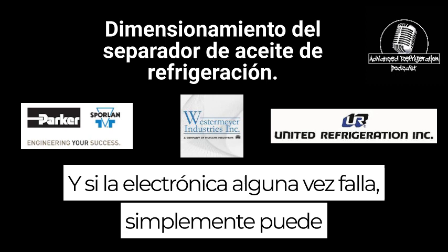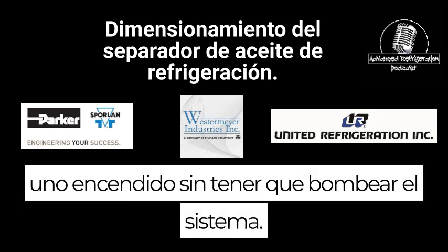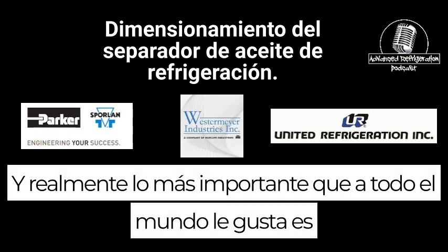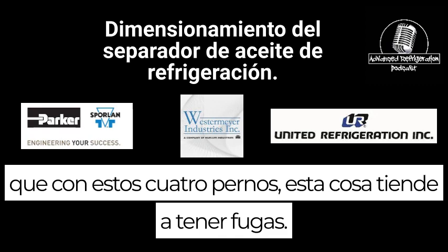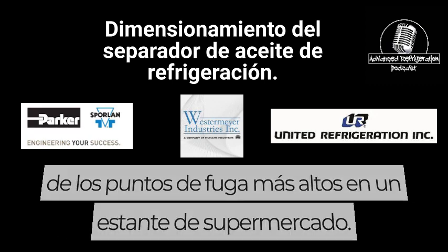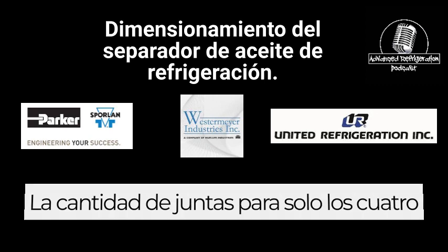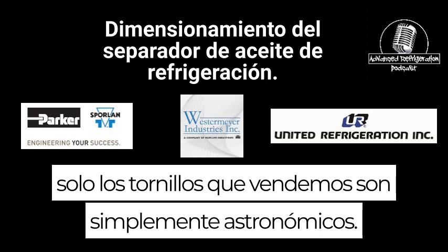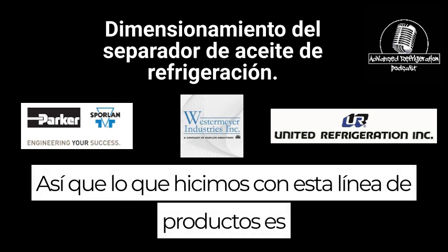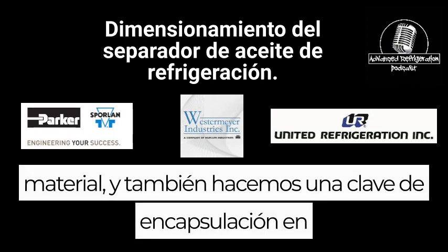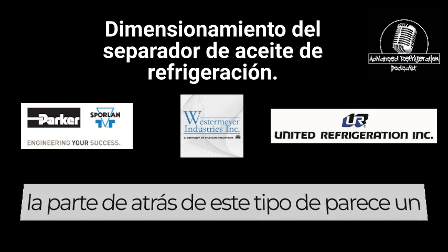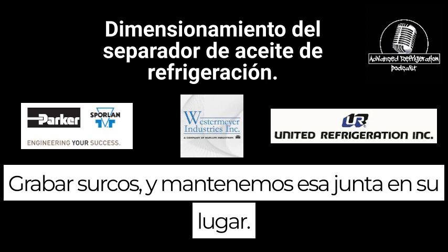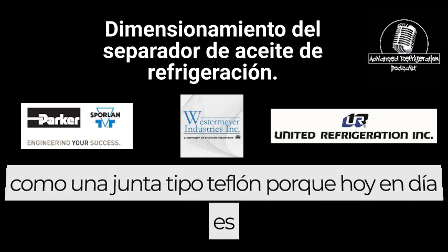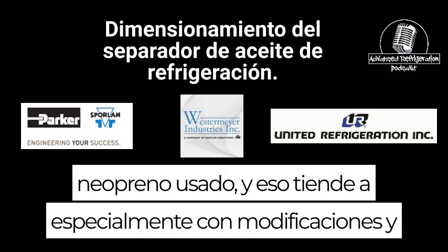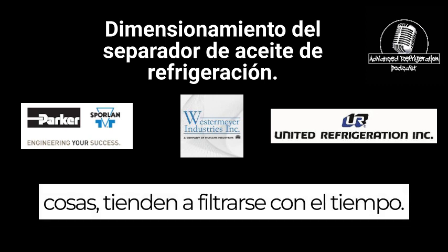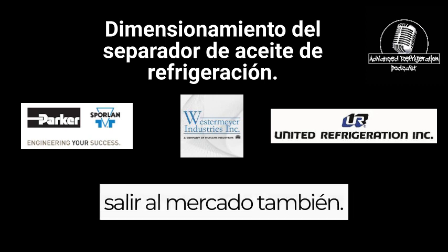If the electronics ever fail, you can just pop that off the sight glass and put a new one on without having to pump the system down. The big thing everybody likes is that the 4-bolt tends to leak. In our market research, it's one of the highest leak points on a supermarket rack. The amount of gaskets we sell for just the 4 bolts alone is astronomical. So with the retrofit kit, we developed a different gasket material, and we also do an encapsulation key on the back that looks like record grooves and holds the gasket in place. It's a Teflon-type gasket, because today neoprene is used, and especially with retrofits, it tends to leak over time.